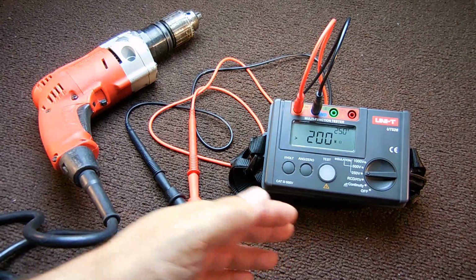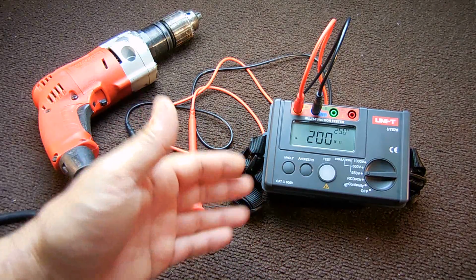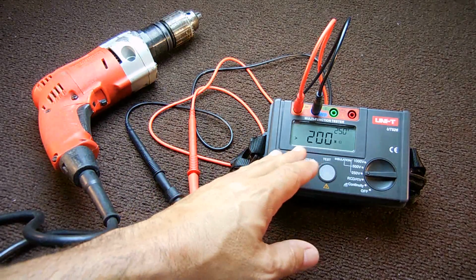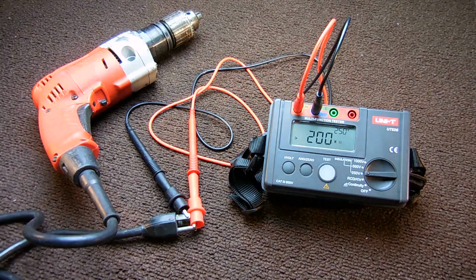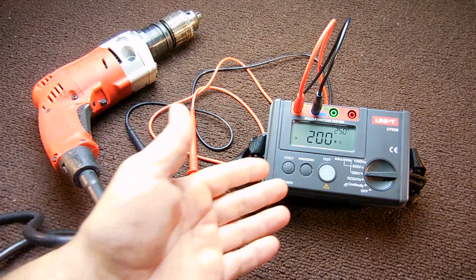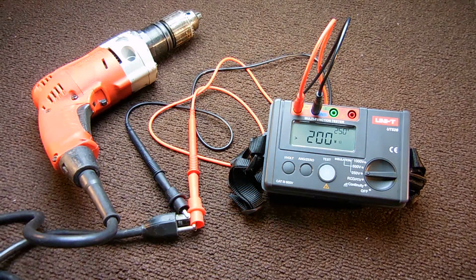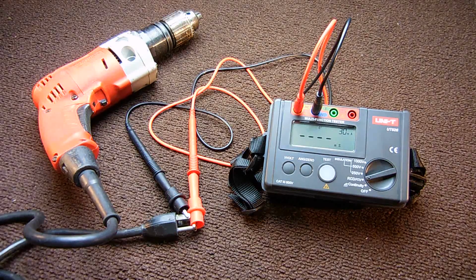So you'd have all the different readings side by side, and if they're all the same manufacturer, same model, you'd be able to compare the insulation from one to another. If you don't have more than one, then you just want to make sure you have a high reading. At least 50 megohm or higher should be okay. As that number gets lower and lower, you know the life expectancy of that compressor is getting very close to the end.